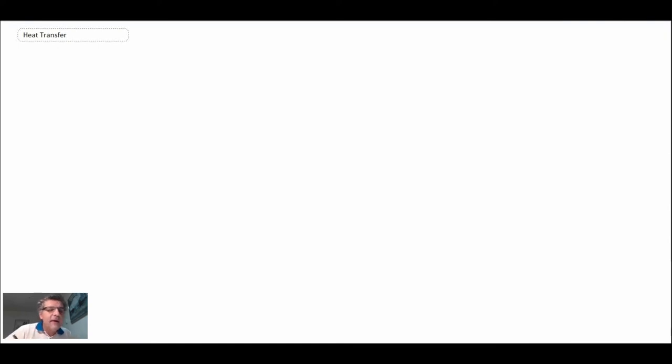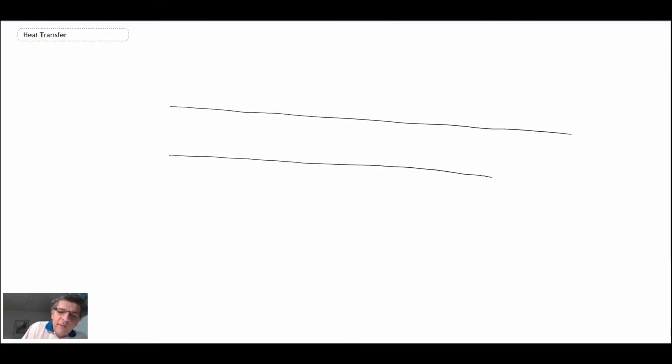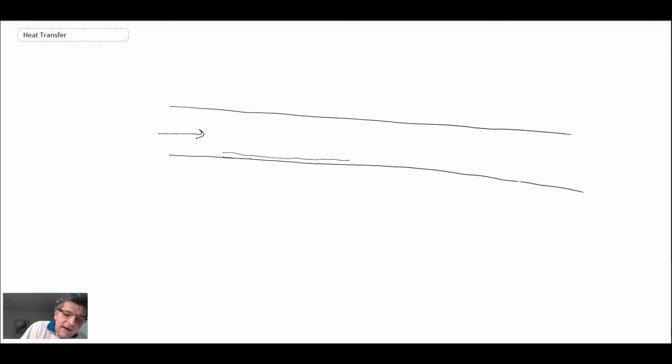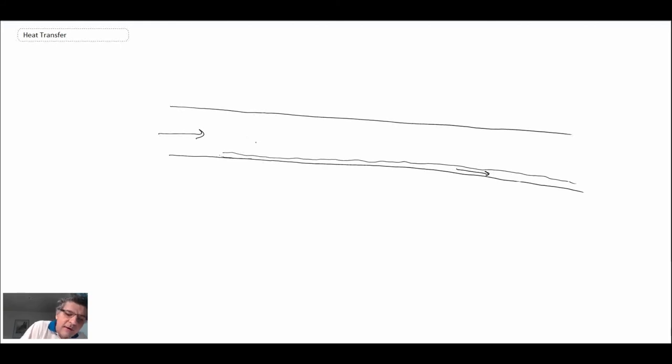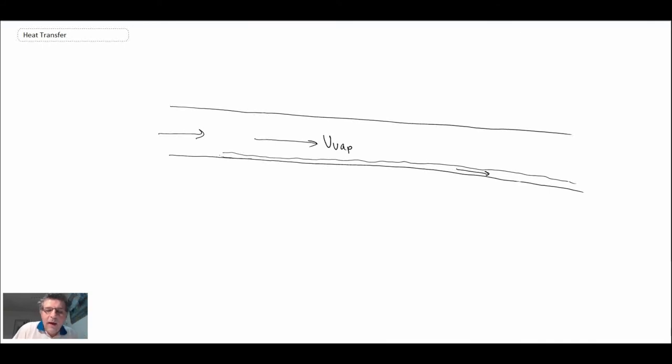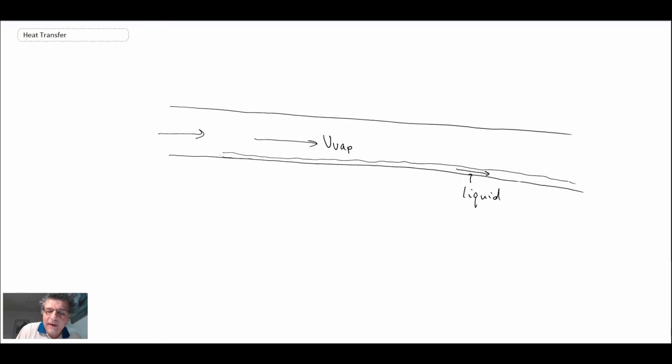If I sketch that out, you would have a system like this. Usually they'll incline the tubes at a bit of an angle, but you would have a vapor going through. You would get condensation forming and you would get a film forming like this. You want to use gravity to draw that down. Sometimes you'll also have your vapor velocity coming through the central core. Then essentially what happens is this would be your liquid and you would have gravity driving that.